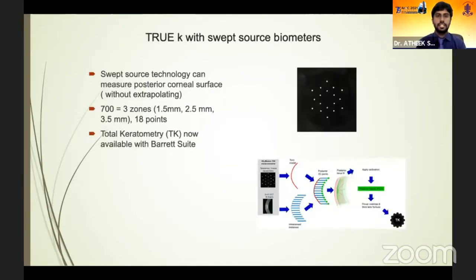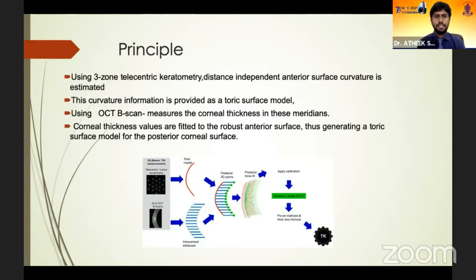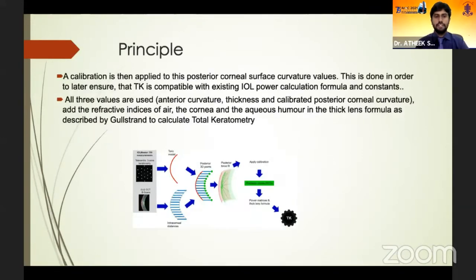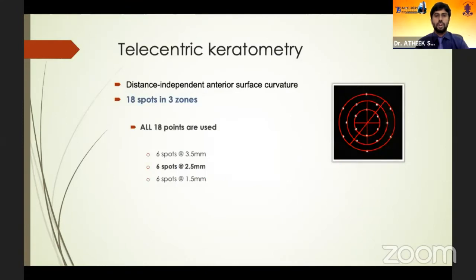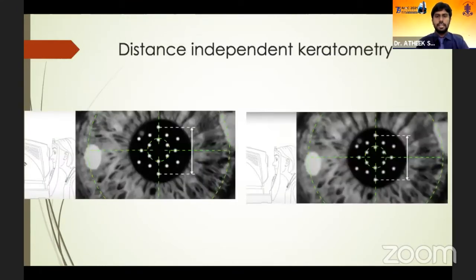With newer swept source-based biometers, we can actually measure the posterior cornea without extrapolation. These use a distance-independent measurement of the anterior corneal surface, and curvature information is provided on a toric surface model. Using OCT B-scan, the posterior cornea is measured at about 18 points, fitted onto the anterior surface, and a toric surface model is generated. Using refractive indices of air, cornea, and aqueous with Gullstrand's principle, total keratometry of the cornea is calculated. Telecentric keratometry means that slight patient distance offset still gives precise values.